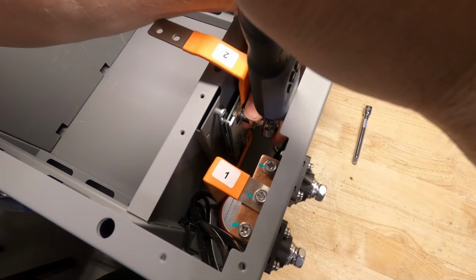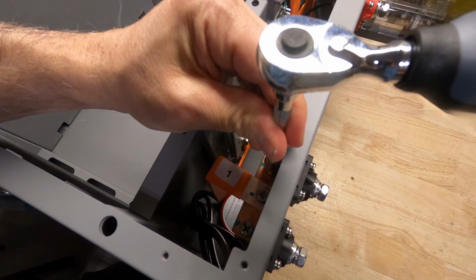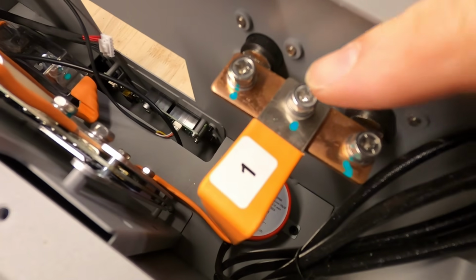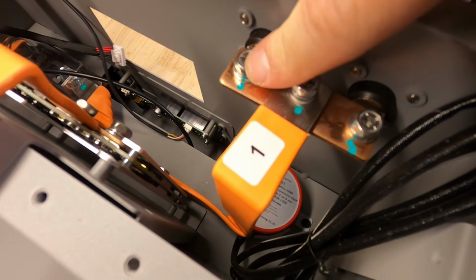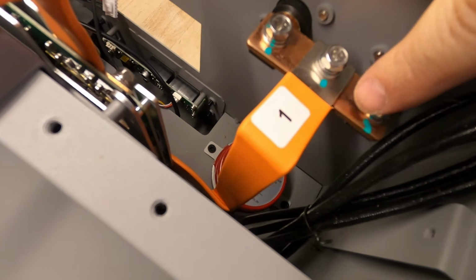Let's build it. So you can see on the battery terminal spanner bus bar here, you can see how off the marks are. That's because I torqued them down to 8 Newton meters. When I checked them with my torque wrench, they were about 4 Newton meters. Well, when I checked the bolts on the BMS, they were 8 Newton meters. So the bolts, they're all M6 bolts, and they all connect the bus bars to the BMS, to the terminals. So they should all be the same torque. So I went with the highest torque, which was on the BMS terminals themselves, so it should at least be that much. So I torqued everything to 8 Newton meters, so make sure to double check the torque on all the M6 bolts connecting the bus bars to the terminals to the BMS.